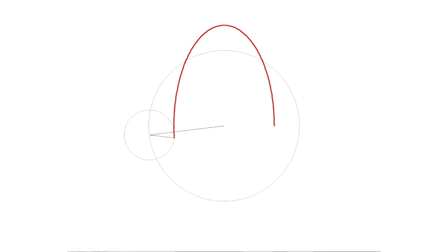Let's talk about ellipse. Imagine that the shaft vibrates on 2 exact circular motions. One motion is in rotation direction and has 1st amplitude. The second motion goes against rotation direction and has the 2nd amplitude. This is the first motion in rotation direction. This is the 2nd motion in opposite direction. What happens if I run both motions together? It is a surprise. The ellipse motion shape is the result.